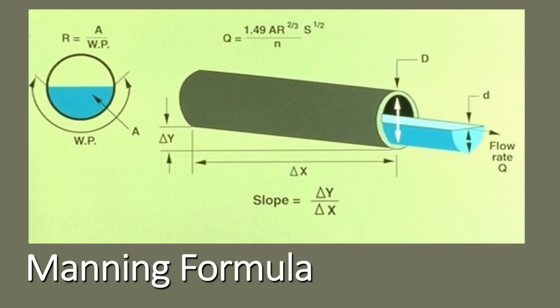But since that doesn't exist, what we need to do is use the Manning formula. In this specific application, we would look at the materials and construction of the pipe, the geometry of the pipe, the flow restriction in the pipe if it's corrugated piping. But more commonly, you're going to use that in open channel flow measurement, like in streams or even rivers.